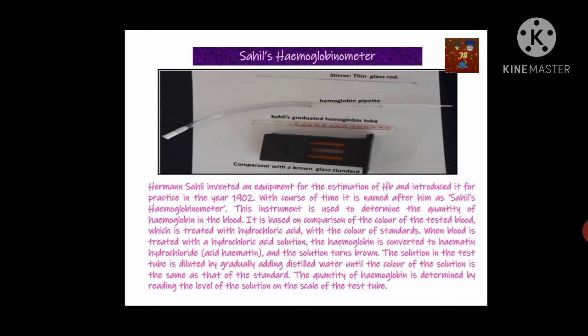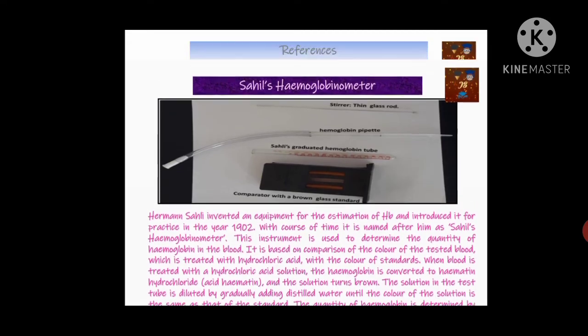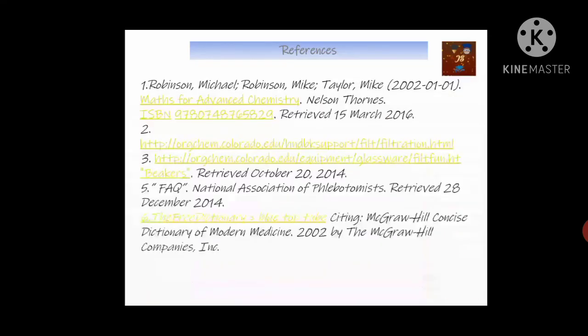The mixture of HCl and blood is converted into acid hematin, which turns the color brown. This Sahli's graduated hemoglobin tube is placed in the middle of the comparator box, and drop by drop distilled water is added to dilute the solution. The color is then compared with two reference color columns in the comparator box. This is a completely manual process, useful for field conditions where electricity is not available, as the entire apparatus comes packed in a portable box.